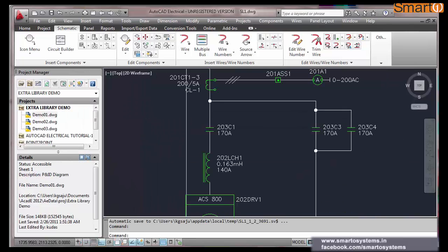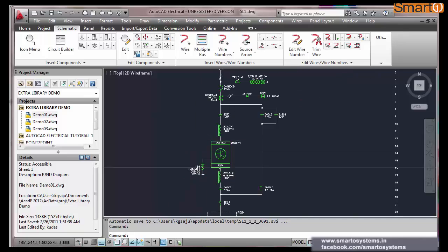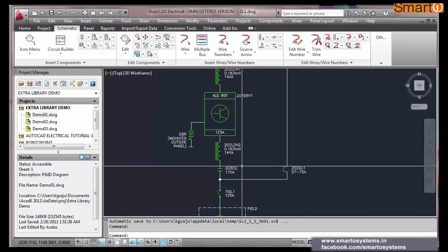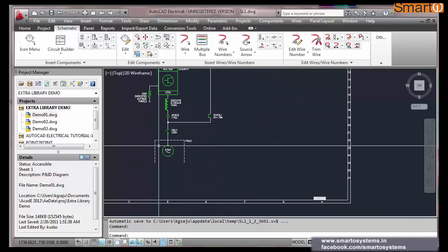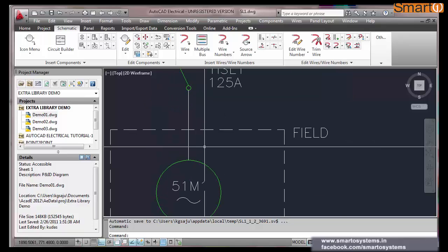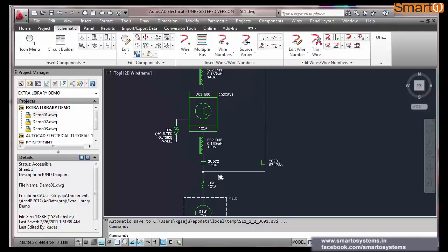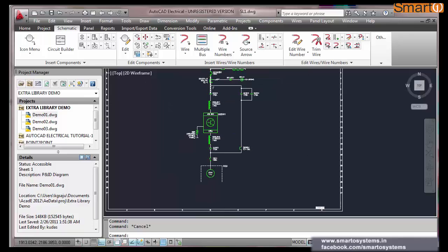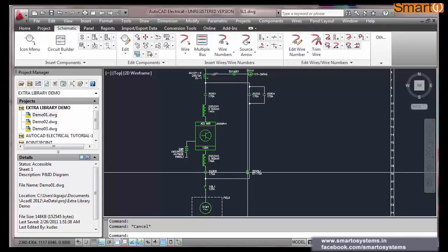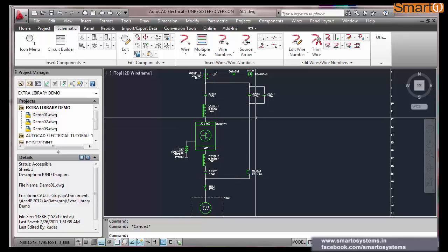Now, here I want to draw the drives, line chokes, contactors and all. If you see the circuit, what we are doing here is we want to drive a motor. We are controlling this motor through a drive, a VFD. But there is a bypass, because in case the drive gets a fault, the customer cannot stop the motor. So he wants the motor to run continuously. In that case, they make a bypass arrangement as well. In case it fails, it will work.